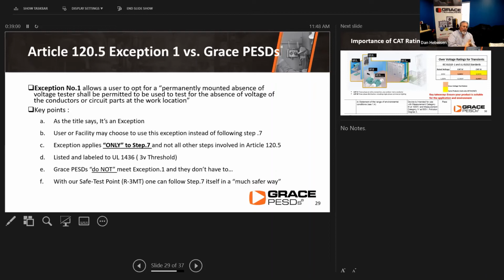And the device has to be UL listed and labeled to UL 1436. The GRACE permanent electrical safety devices do not meet the exception, and they don't have to, because they basically meet the rule in the UL 61010 category rating. The key factor for the safe test points is that with that device installed, one can easily follow step 7 in a much safer and more convenient way.